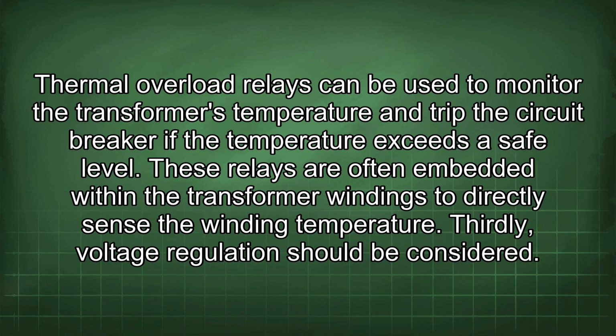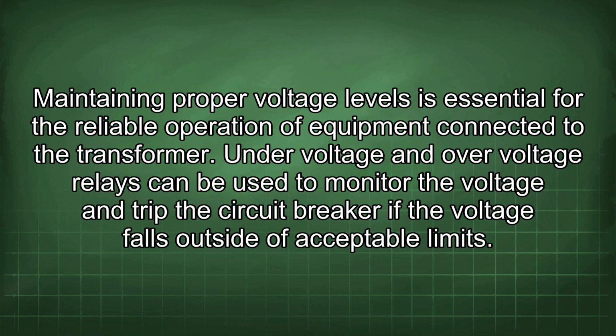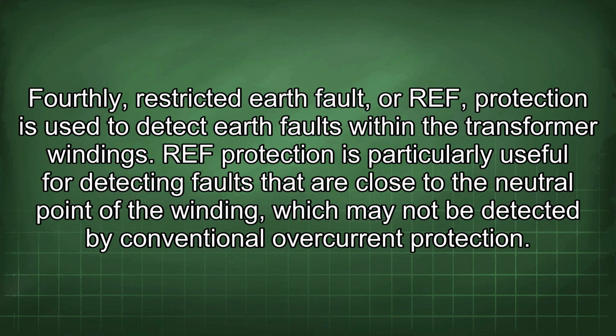Thirdly, voltage regulation should be considered. Maintaining proper voltage levels is essential for the reliable operation of equipment connected to the transformer. Under-voltage and over-voltage relays can be used to monitor the voltage and trip the circuit breaker if the voltage falls outside of acceptable limits. Fourthly, restricted earth fault, or REF, protection is used to detect earth faults within the transformer windings. REF protection is particularly useful for detecting faults that are close to the neutral point of the winding, which may not be detected by conventional overcurrent protection.